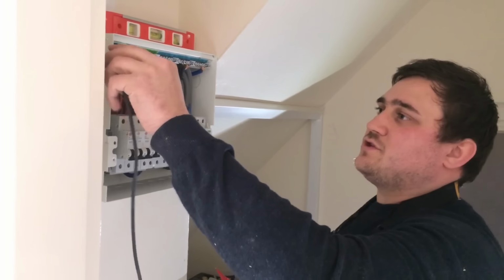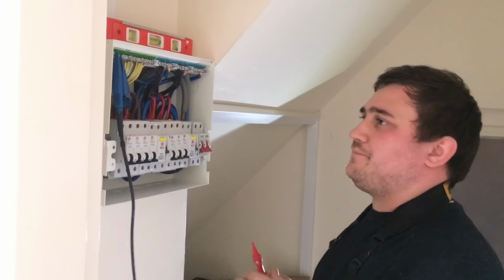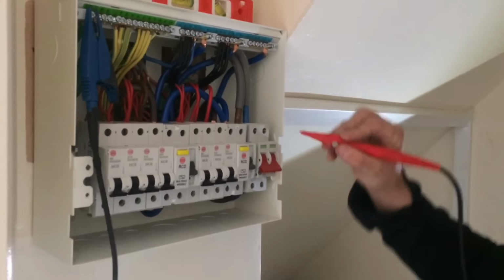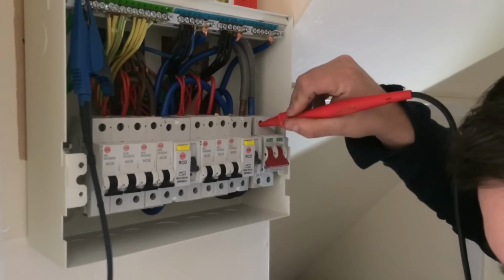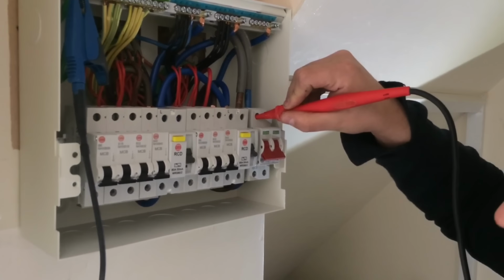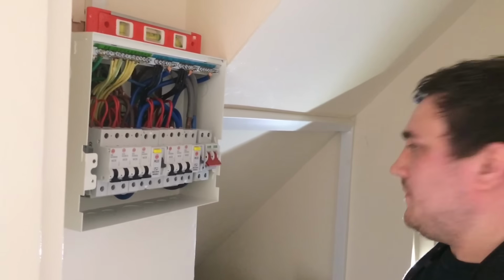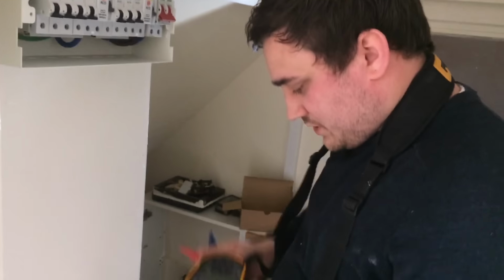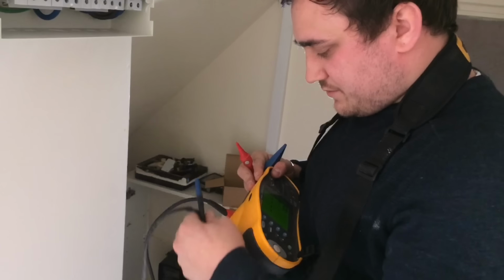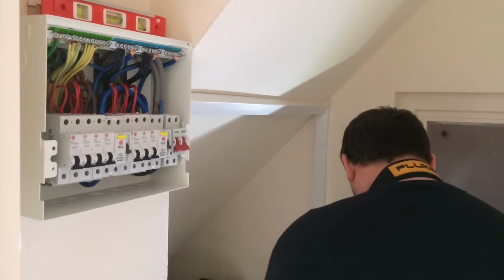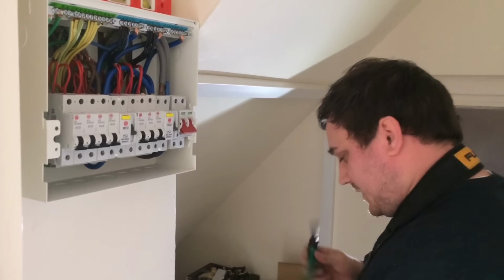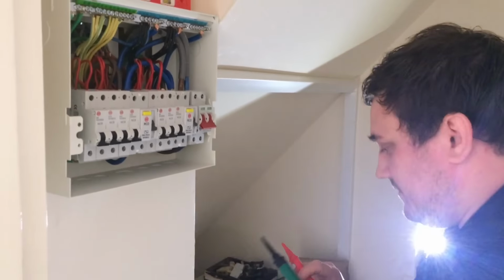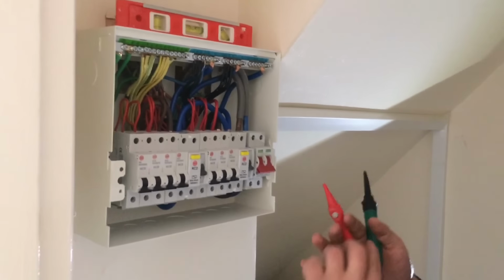So first of all, we're going to clamp onto our main earth bar and into the top of the main switch we're going to do our prospective earth fault current, 1.2 kA. I've got to switch my meter around because we're going to do the prospective short circuit current, which is between line and neutral. And for this we're going to go on to the top of the main switch.